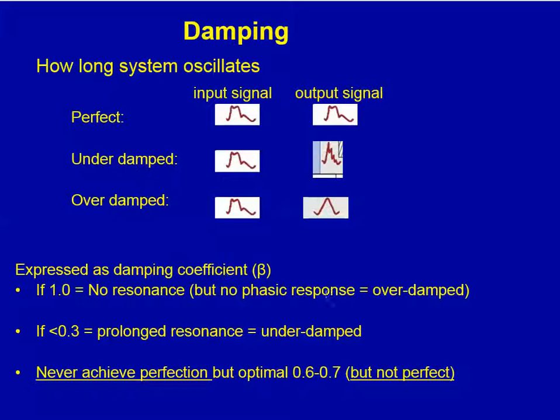The amount of damping is expressed as a damping coefficient which goes from zero to one. When there is complete damping there is no resonance, but there's also no phasic response. Conversely, if it's less than 0.3 there's prolonged resonance and it's under-damped. No degree of damping is perfect — it's always a balance, and empirically a damping coefficient of somewhere between 0.6 and 0.7 is ideal.